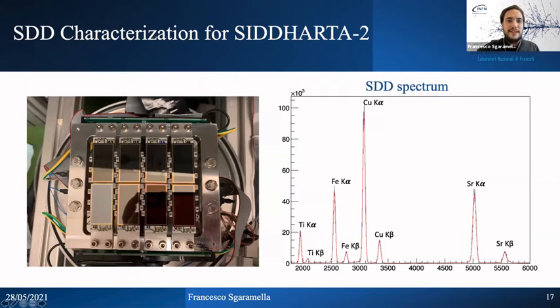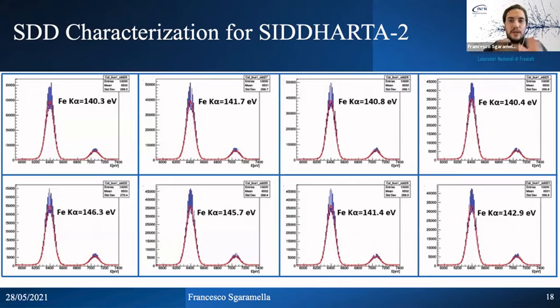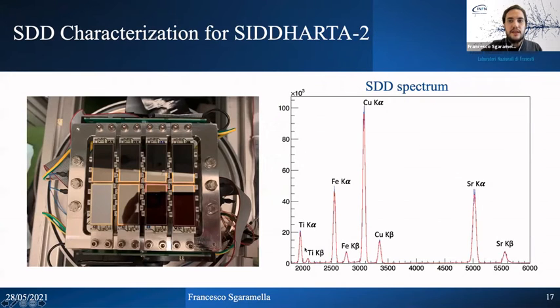Okay, these are the detectors installed on the mounting device. There are, but are not visible, two heaters placed here and two PT100 to control the temperature of the detectors. And this is an example of an SDD spectrum obtained after the characterization run. From the fit parameters, we evaluate the linearity and the energy resolution for each SDD. And this is the result of the characterization of one array. We can see 8 working channels with the resolution for the K alpha iron line. After the characterization, the array is ready to be installed in the Siddhartha setup.